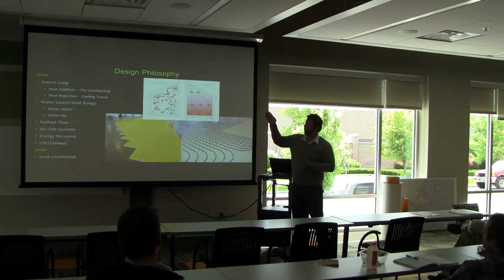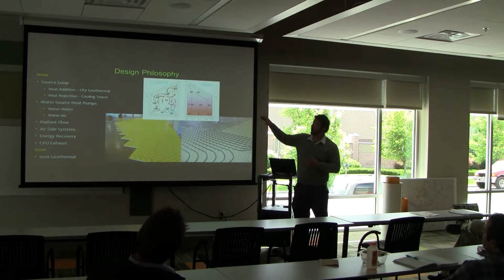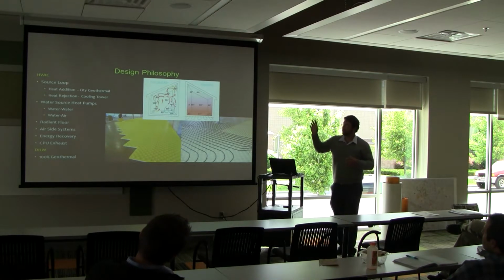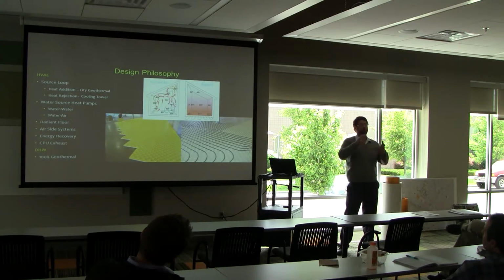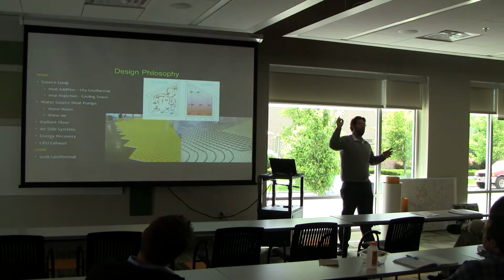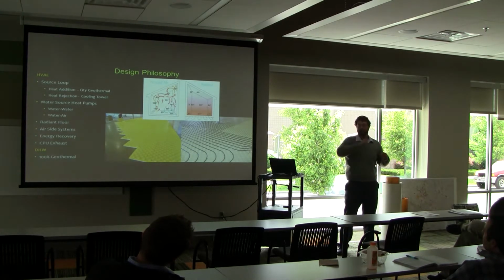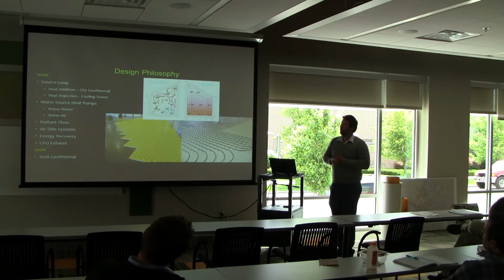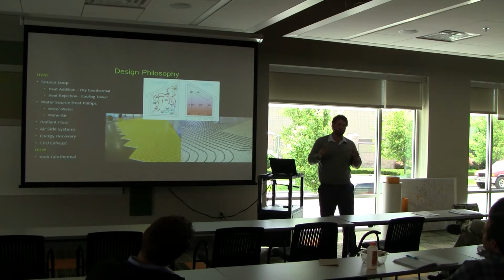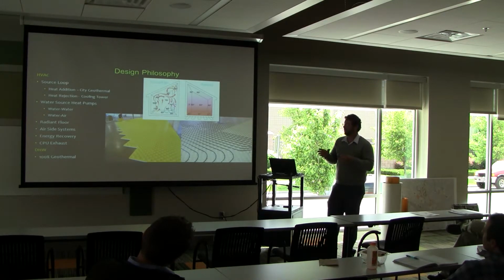So there's a schematic on the next page. However, the way that the HVAC system works is this concept of a source loop. So there's literally a hot water loop that goes around this building, which is kept at about 70 degrees. It's variable. We found that we didn't want to just keep it at 70 degrees for a reason. I'll get into that in the next slide.